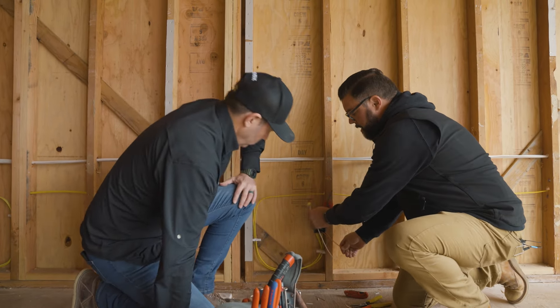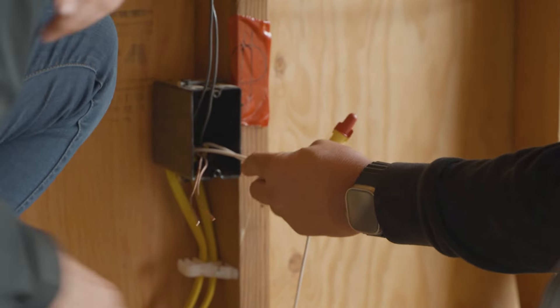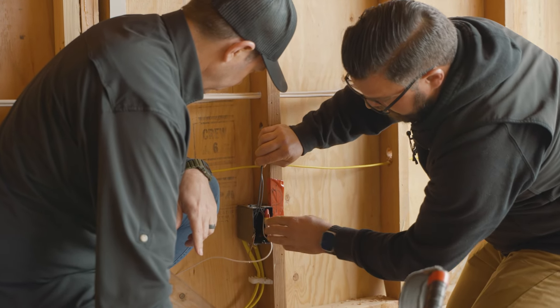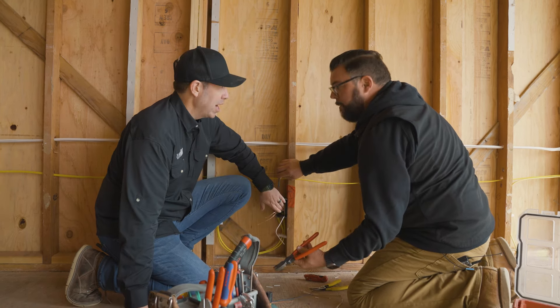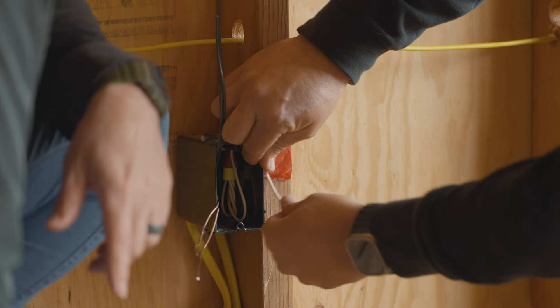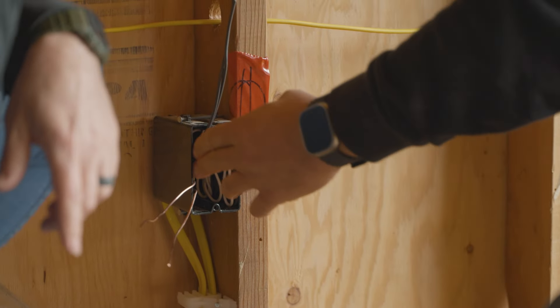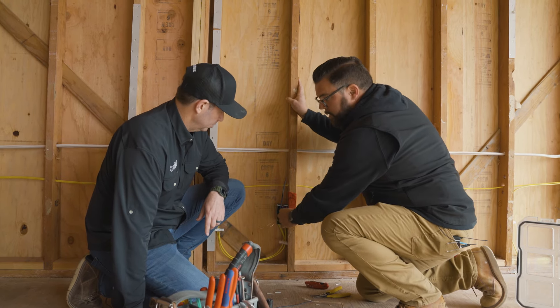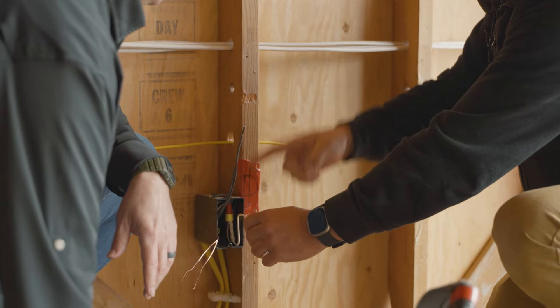I'm going to show you how we tuck these wires in the box. Remember that distance I gave you? We like to tuck it in nice and slow. See where that's going to live? That's why we judge the length — it varies box to box, but I want that in the back because we need room for the device to live in there. And then watch this — up, down. Look at that: ground, neutral, hot, like three little soldiers ready to go. They'll drywall and really all we'll have to do is come back. That's what I call the accordion — or a W.